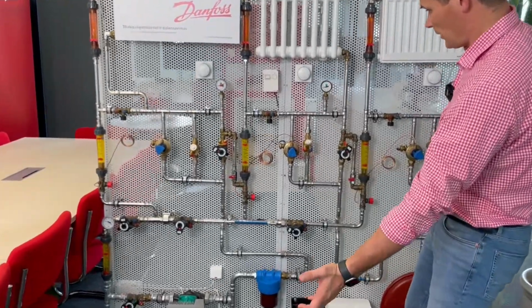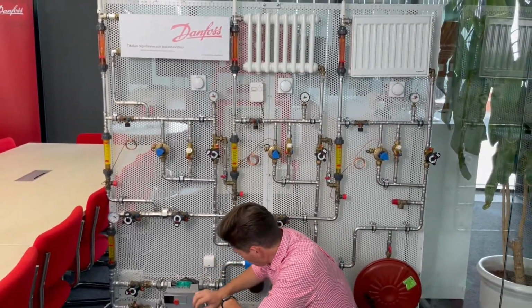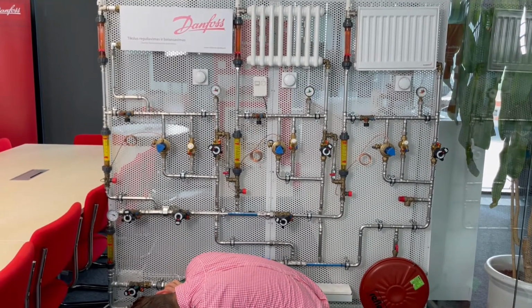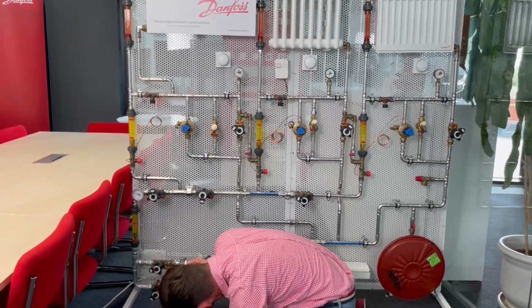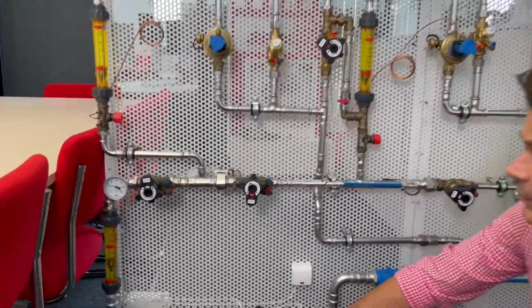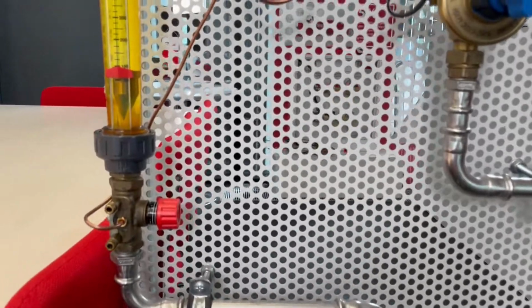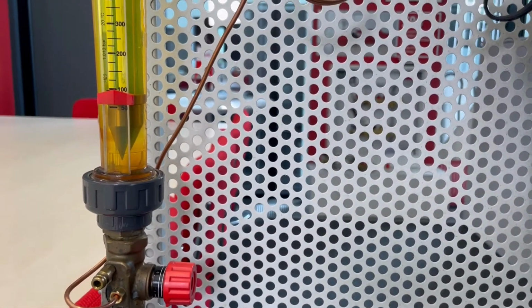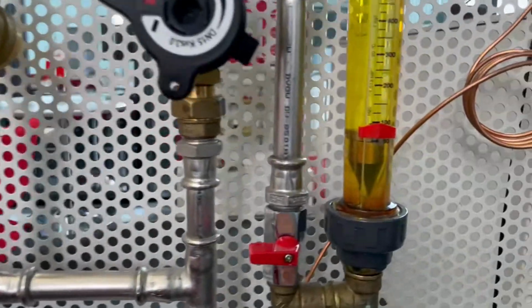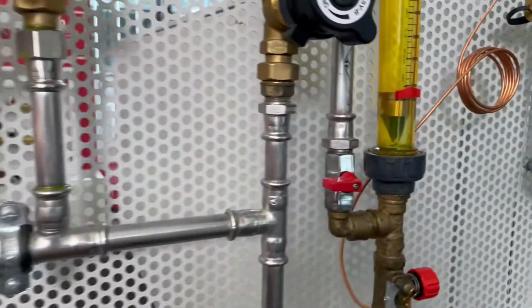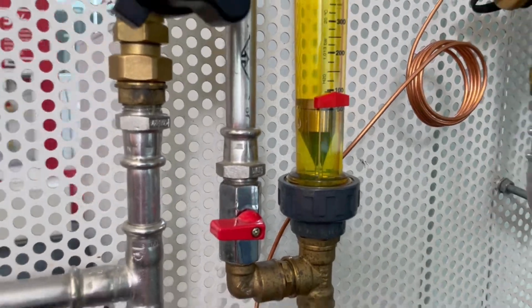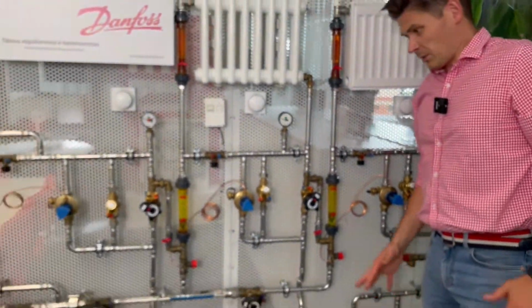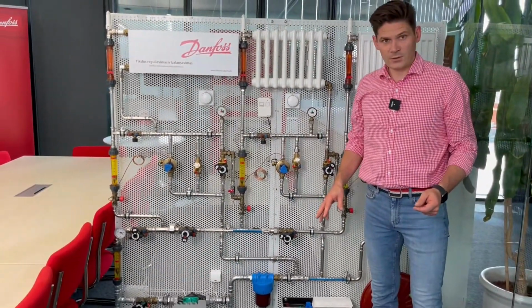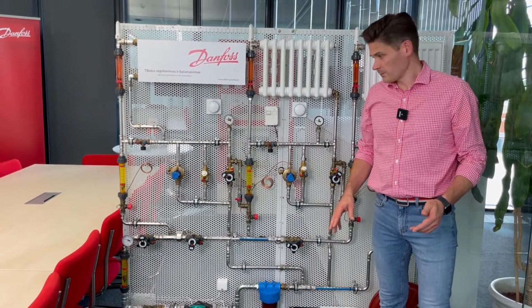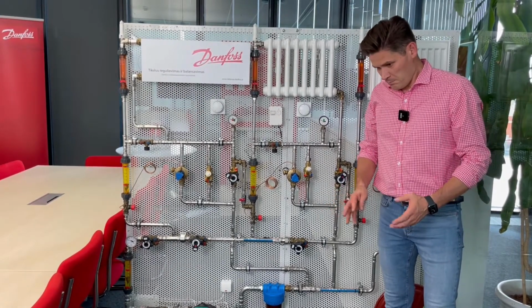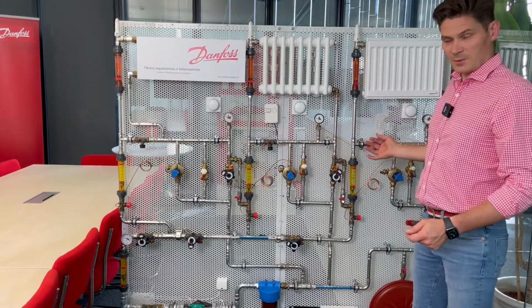Okay, so I already made the settings. I switch on the pump, and I immediately go to the pump setting, and I increase the maximum pump head to have the right flow everywhere. And let's check now how much flow we have in each riser. 100 liters, almost 100 liters, and here almost 100 liters. Maybe it needs some readjustment, but more or less the accuracy is quite good, plus or minus 10% is normal. And without measuring tools, we already commissioned the system without water.